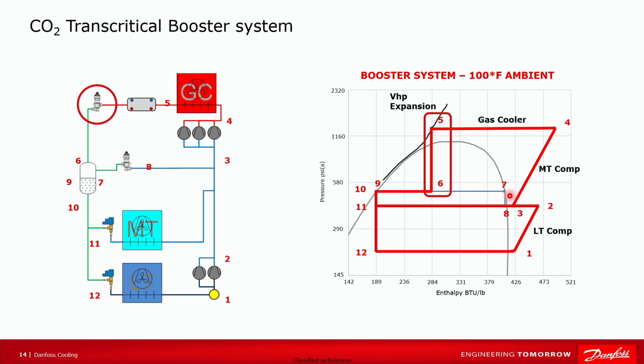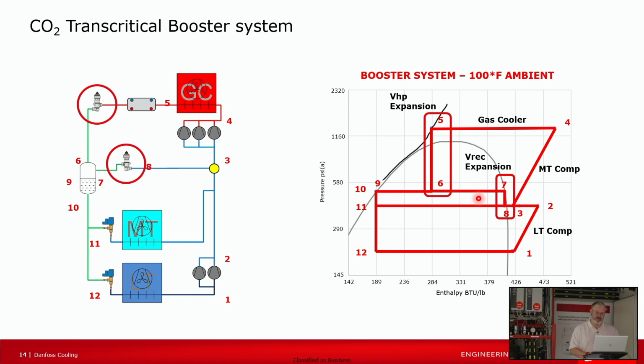The last piece of the puzzle here is point 6 to 7 back into the medium temp suction header, and that's another expansion. If you'll recall, we had a 520 pound set point for the flash tank, 400 pounds for the medium temp evaporators. So that's our set point for medium temp suction. That's an expansion, so we're coming from the flash tank over to the receiver valve and then back into the medium temp suction. And that kind of completes our cycle. There are typically questions around that, so hopefully we'll see some in a few minutes.